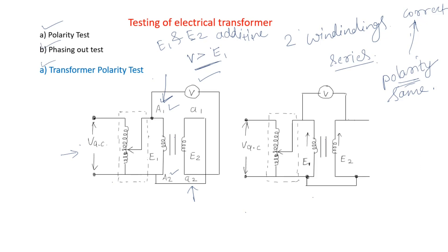In case it is not so, if we don't see this in the output, then polarity marking is not correct. So the marking of any one side has to be changed. Test is again carried out by making connection as shown in the figure.